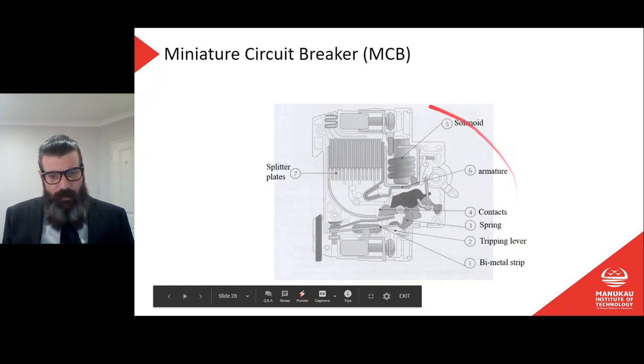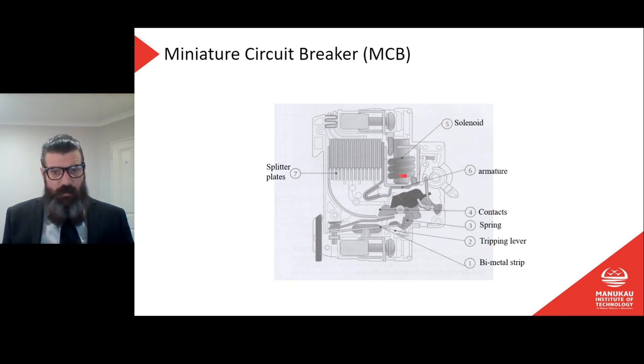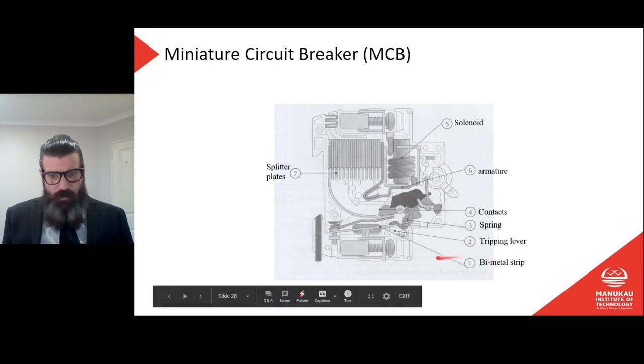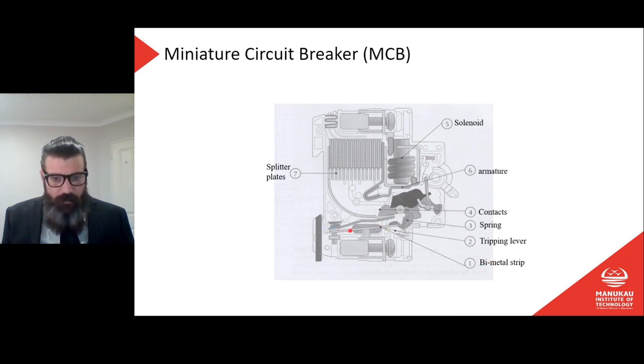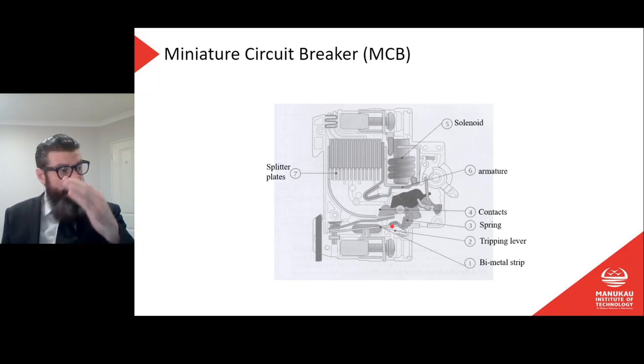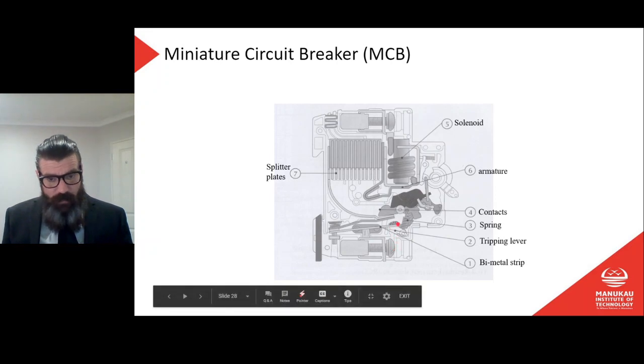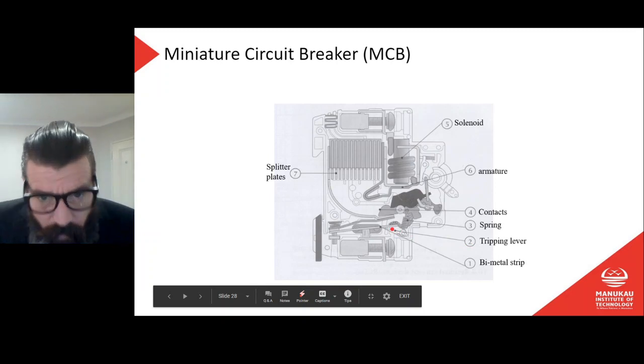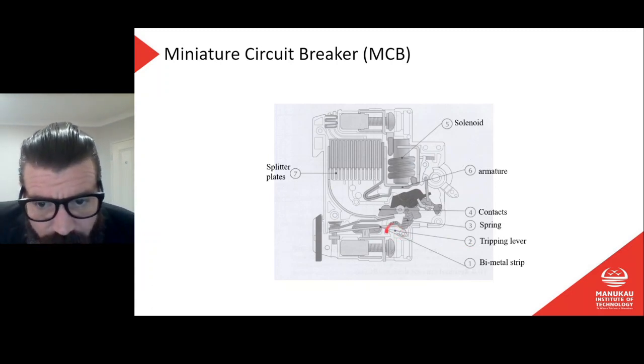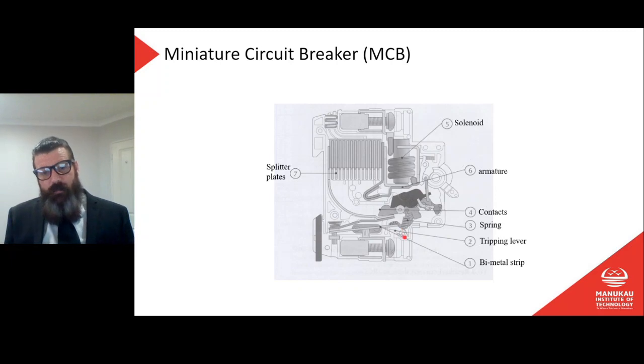Cool. And here's our diagram. You do need to have a good look at this and try your best to memorize those parts. We have the solenoid here. Let's start at number 1, the bimetal strip. So that's this guy here. Remember, our bimetal strip is just like any other bimetal strip. When current flows through it, it'll heat up. When too much current flows through it, it's going to heat and bend. It's going to bend away, bend downwards, and that's going to activate the tripping mechanism, which is number 2, the tripping lever in here. Tough to really see what that's pointing at. Nevertheless, as it says there, number 2 is the tripping lever.